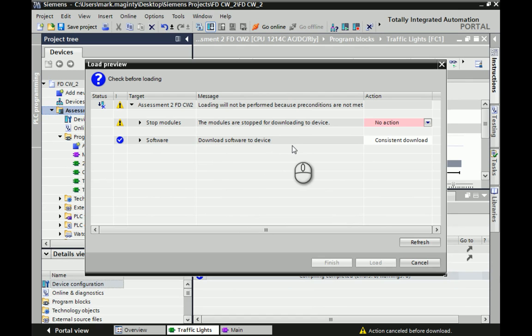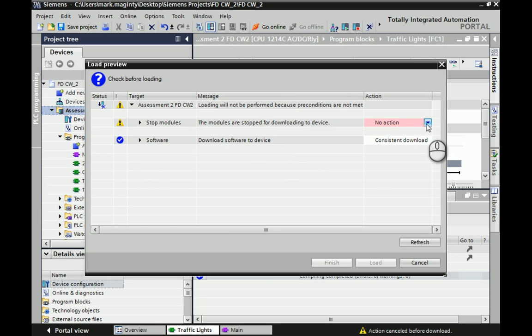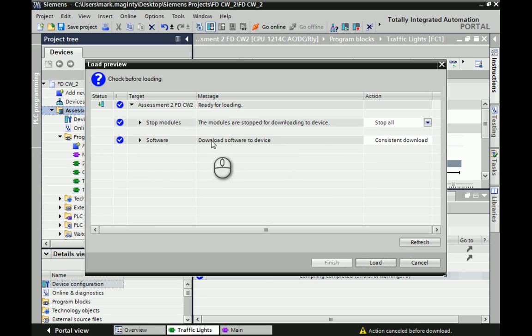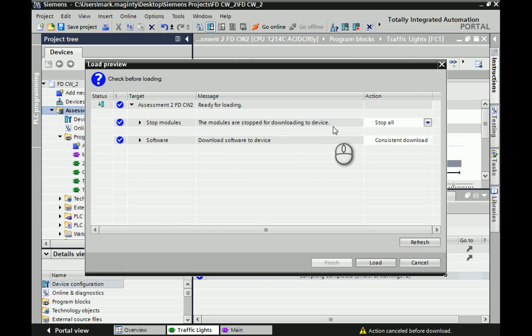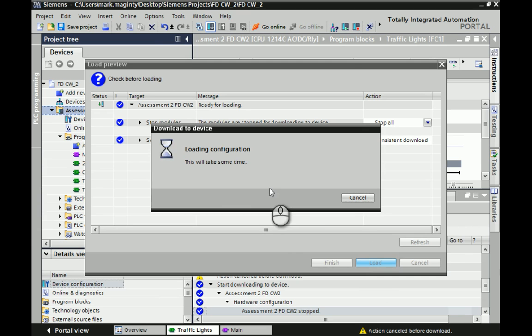It'll then go into another window, which is a load preview window. Anything on here that has a warning symbol on the left-hand side or a drop-down action, you need to change it so it all goes to a blue tick. Most times, it will just be changing this one to a stop all. The basic premise is the modules are stopped for downloading to device. The PLC needs to go into a stop feature before you download so it doesn't crash or do anything wrong with the internals. Select Stop All, and then you're able to hit Load.